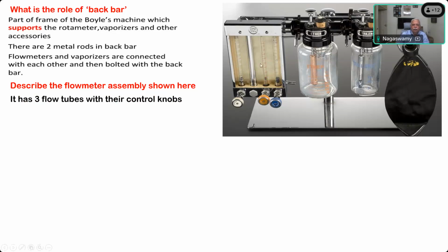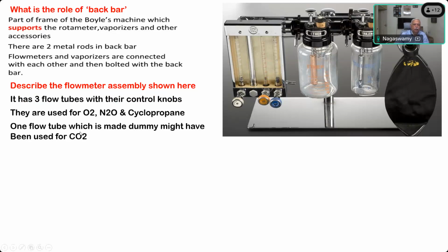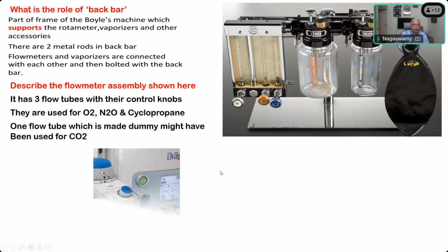So they dummied it and they stopped using that. But other gases they are using. So this is a very, very old type machine, where we had one such machine in our Stanley, which was routinely kept in the exam, and the examiners are very fond of asking this color coding knob for cyclopropane. So it has three flow tubes and their control knobs. They are for oxygen, nitrous oxide, and cyclopropane. The one flow tube which is made dummy may have been used for carbon dioxide.